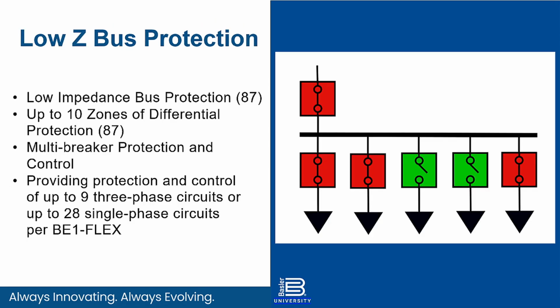of hardware. As we start to look at the larger range of what somebody might be able to do with a protective relay, low Z, meaning low impedance, bus protection happens to be one of the more hardware intensive applications that protective relays do. And they do that because they need to monitor all of the current inputs on all of the lines that are going into and out of the bus. So if you're doing a three-phase bus differential, that'd be phase A, B, and C for every single breaker, assuming you're talking about a three-phase system. So in this particular example, it would be the main breaker and 5 feeders, so 6 times 3 is going to be 18 current inputs that would have to come into the protective relay in order to do this as a low impedance bus differential. The Flex can certainly do that.